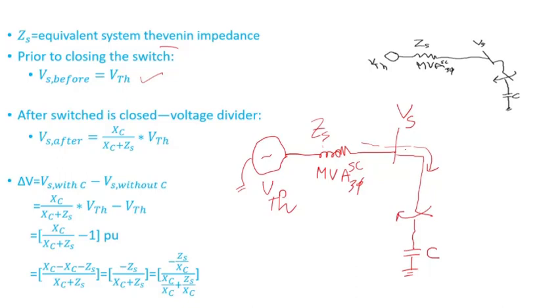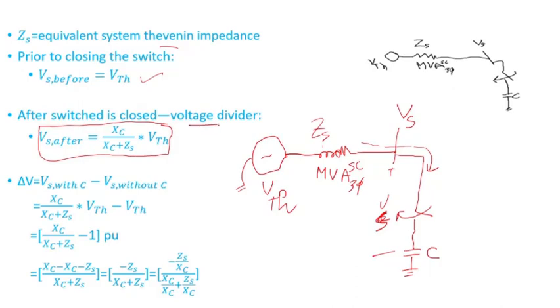After the switch is closed and the capacitor bank is in service, we can apply a voltage divider. VS after closing the switch equals the impedance of the capacitor bank divided by the sum of the capacitor bank impedance plus the equivalent Thevenin impedance, times the Thevenin voltage. That's the Thevenin voltage divider applied here.